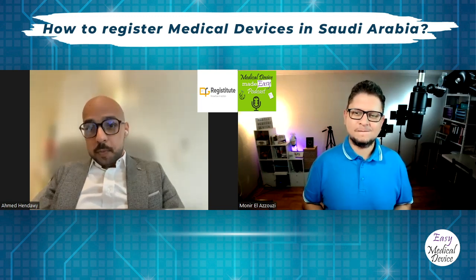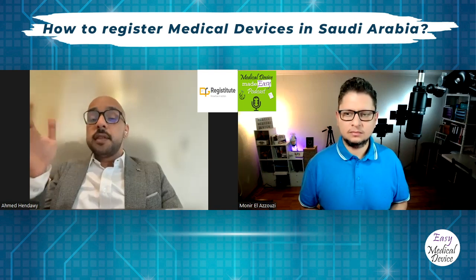Well, there used to be a pathway for class one non-sterile and non-measuring products where the importer is the owner of the product. They submit a very simple form or request to SFDA. It's almost like the self-declaration in Europe. But this was implemented only until September 2022. After that, all medical device or IVD products have to follow the technical file assessment, providing the technical file documents to obtain the certificates. So this method was there until September 2022, but it stopped, and all certificates issued before that are still valid until their expiry date. After that, they need to submit the technical file to SFDA to obtain the certificate.